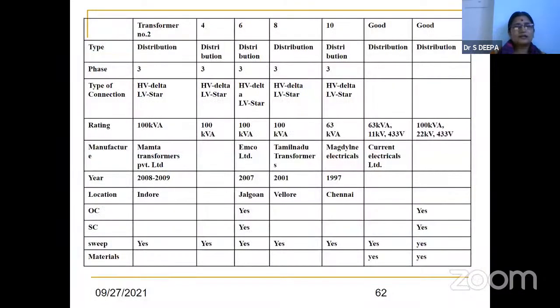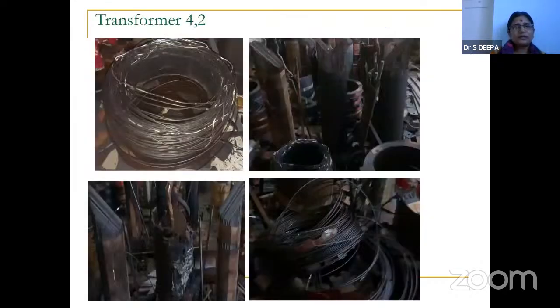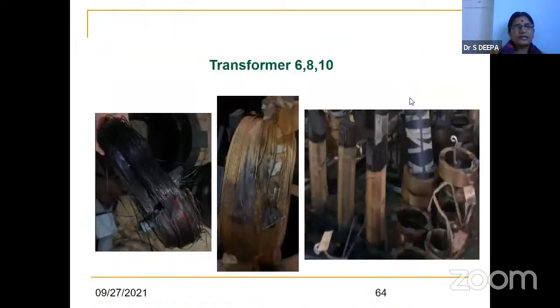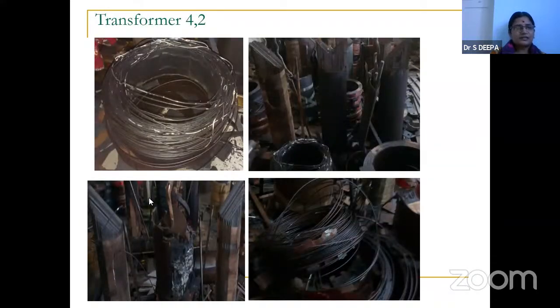Okay, so next, we got nearly 10 different transformers. We named them, took the specific data, and first we opened them. Before opening the transformer, I had done the sweep test, and after opening also, we'll see how the transformer looks. This is how our transformers are on the distribution side. Sometimes the high voltage turns, here we have the low voltage turn near the core, has burnt and got stuck with the core, and coil movement. So this is the fault.